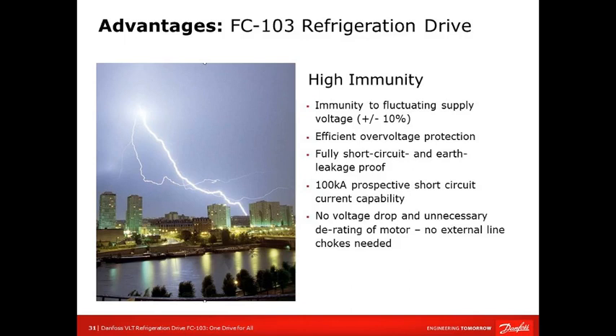Again, what we're trying to do is really identify anything that can happen prior to loss of uptime. For example, if you're in areas where there are power outages, the Danfoss drive has the capability that, if it's a quick power drop, we can actually keep running without losing the motor. You hear stories where maybe they lost power over a weekend and then the whole process stops. So there are some things built into the Danfoss drive. We want to keep you running longer, and we do a lot to identify a problem before it even happens, for example short circuit and missing phases on the motor.